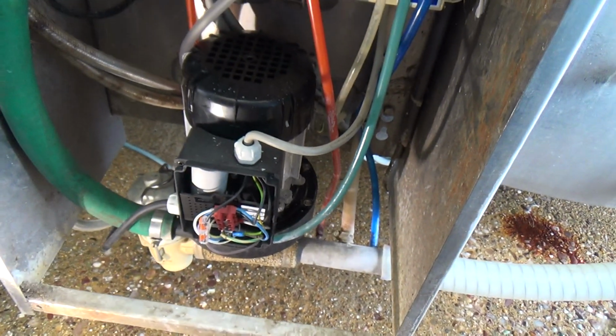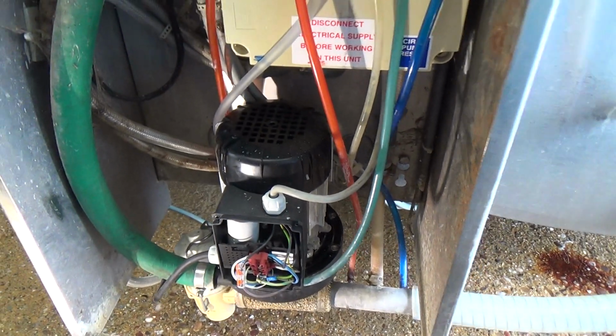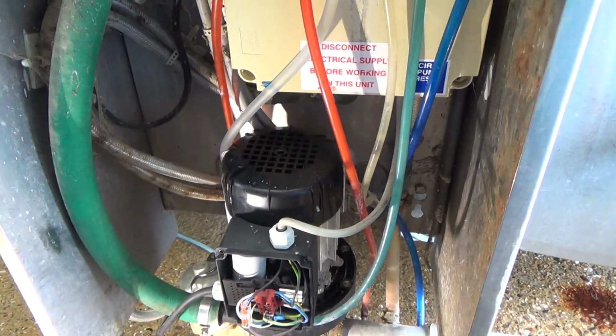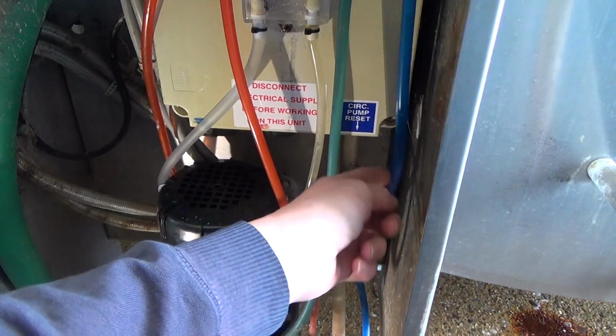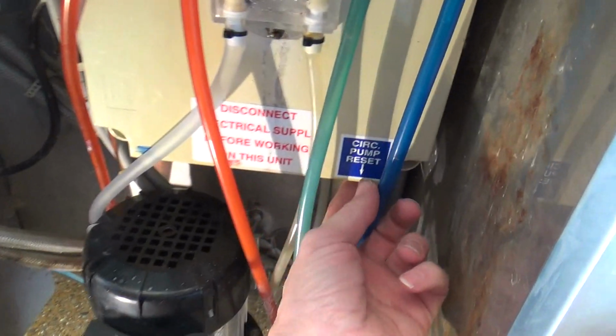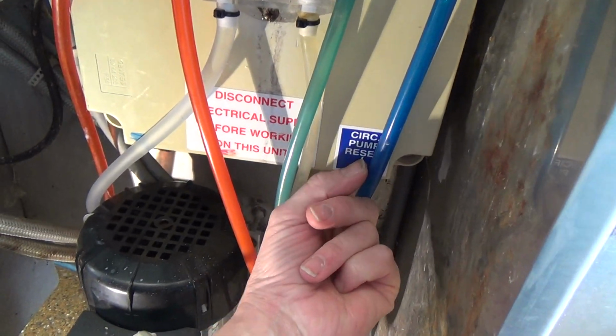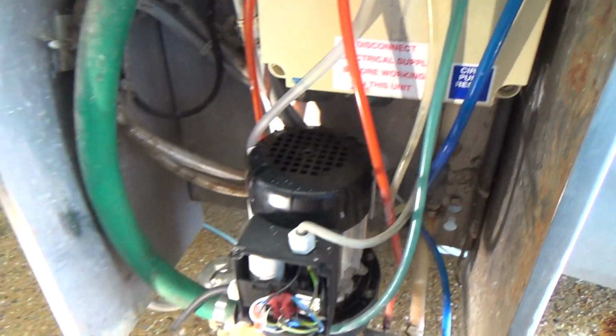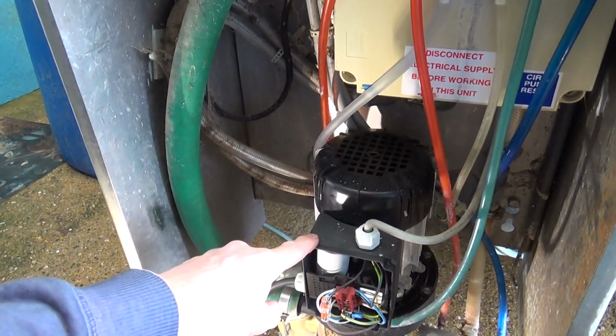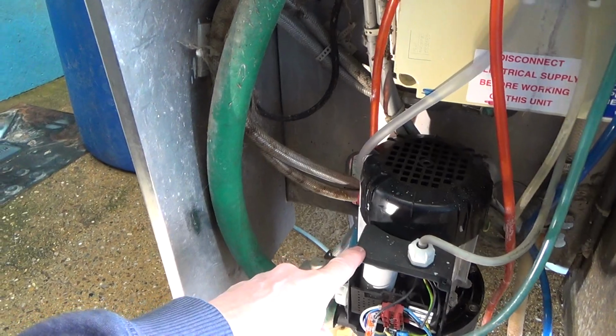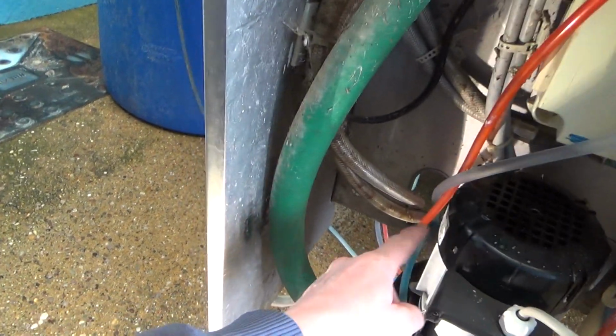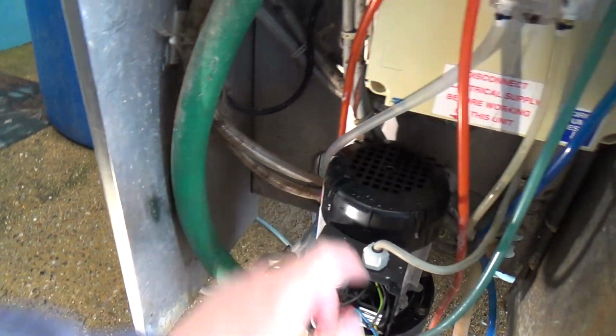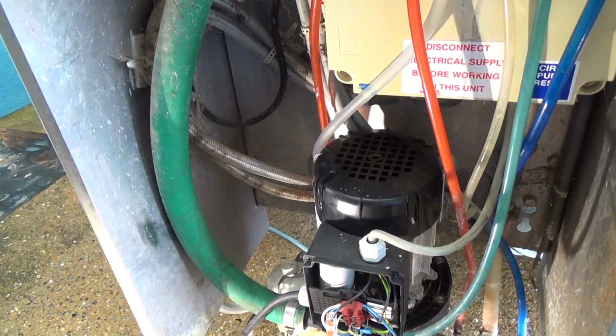Okay, spoke to the customer and we've got a slightly different story to the one we had earlier. The trip that was tripping was this one here, which is this little thermal overload for the pump, which they've had to reset a few times now. This could be because we've put a new pump on here, which is probably slightly bigger than the original, because this is a 270 and the originals were 250s, I think. Although this might have had a 270 on because it's quite a big tank, but it might have been a 250.